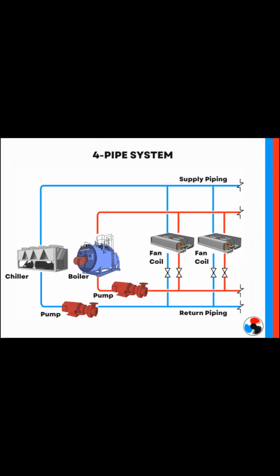Hydronic water can be run through fan coil units, cabinet heater units, and other emitters that resemble forced air systems, but these units typically don't have filters because of their low power fans. It's possible to have the air filtration benefits of forced air in a hydronic system using high power fan coil units, but you'd be paying to move the heat twice, once with pumps and then again with blowers.